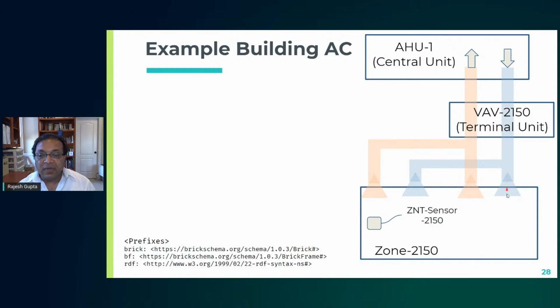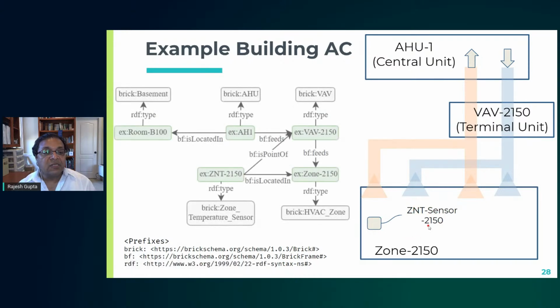and so this is the air being served. This is the air being removed. So this is the supply air. This is the return air. The air handling unit might be doing some cleaning here, or recycling, or temperature control, or humidity control. And you have sensors. So for example, you may have a ZNT sensor in this particular room. So you say, okay, here's how the graph looks. It looks complicated, but it's really nice. I'll walk you through this.